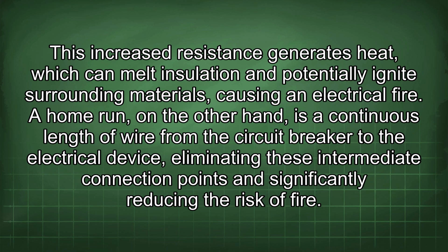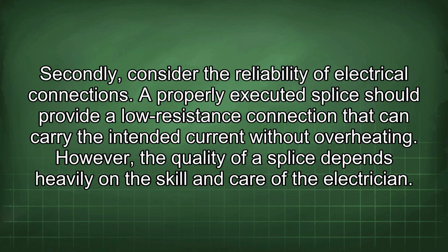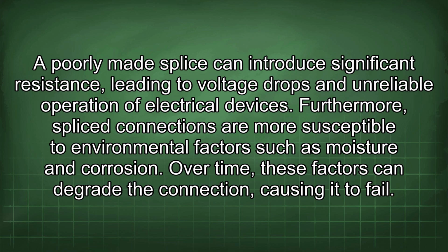A home run, on the other hand, is a continuous length of wire from the circuit breaker to the electrical device, eliminating these intermediate connection points and significantly reducing the risk of fire. Secondly, consider the reliability of electrical connections. A properly executed splice should provide a low resistance connection that can carry the intended current without overheating. However, the quality of a splice depends heavily on the skill and care of the electrician. A poorly made splice can introduce significant resistance, leading to voltage drops and unreliable operation of electrical devices.